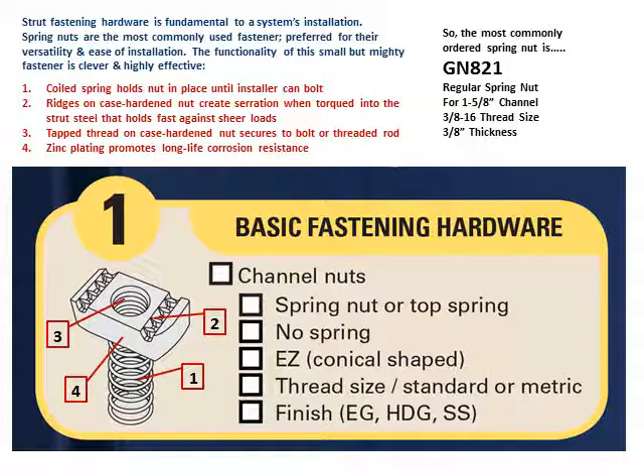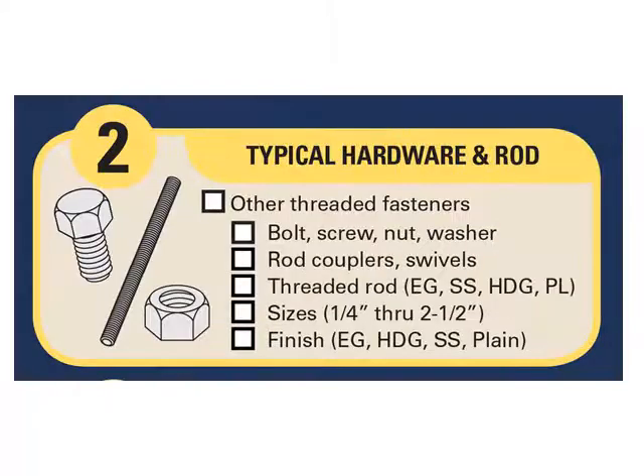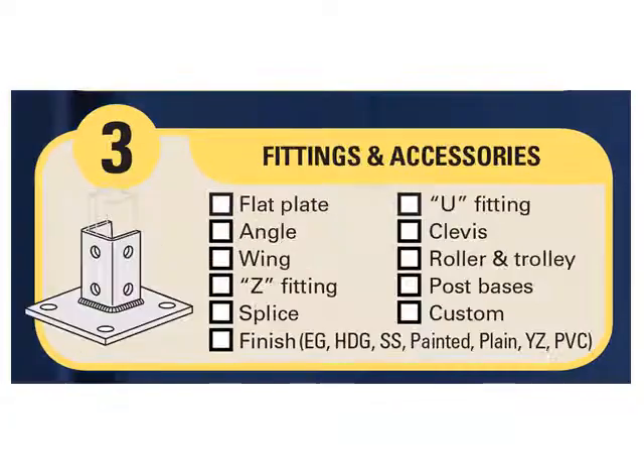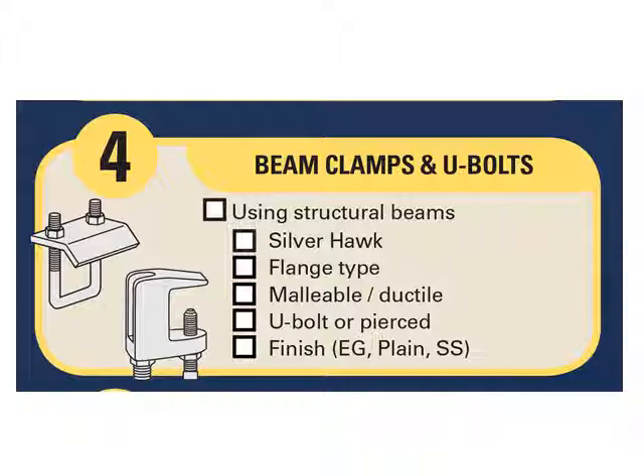The most commonly ordered spring nut is GN821 — regular spring nut for 1-5/8-inch channel, 3/8-inch thread size, 3/8-inch thickness. Number two: typical hardware and rod. In addition to custom strut fasteners, common threaded fasteners such as nuts, bolts, couplers, and threaded rods are fundamental to a typical strut installation. Number three: fittings and accessories. Strut flat and angle plates, post bases, wing fittings, and connector plates are key components that efficiently tie strut channel into a system.